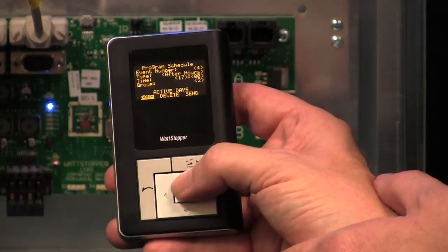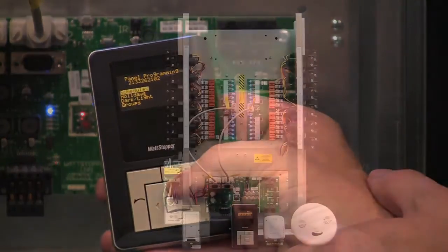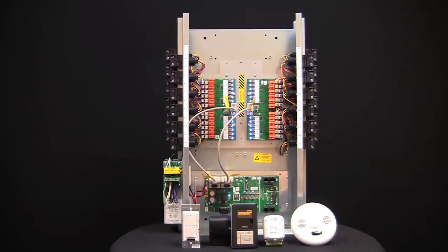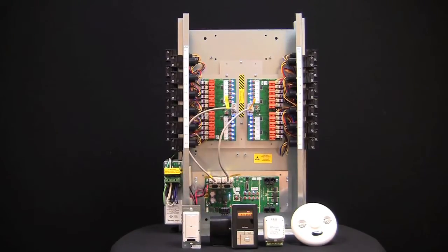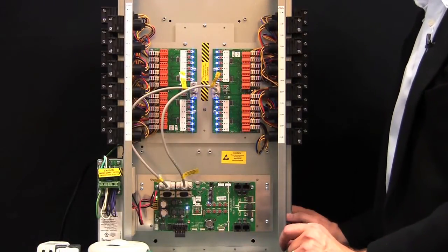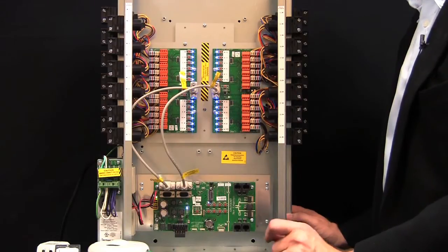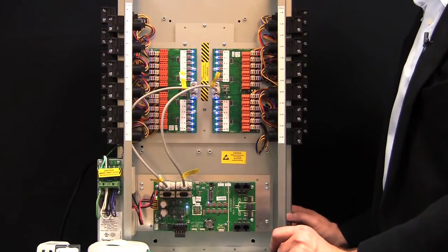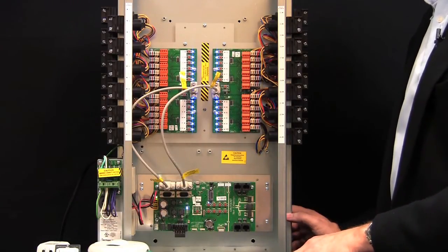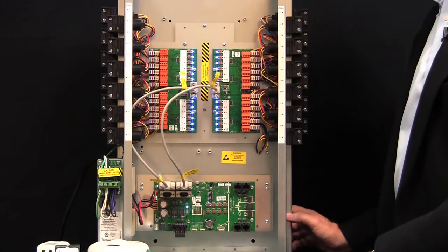We're all done, so I'm going to say done now for these 2 schedules. So what we've done inside this panel is we've used the normal hours and after hours commands to set up a schedule for group number 2. The settings for the group actually will dictate what happens when the loads go to normal hours and when the loads go to after hours. So to review, we've now got 2 different groups that are set up. Group number 1 is following a simple on and off schedule. Group number 2 is actually using the more advanced normal hours and after hours, where we can describe what the parameters are for each part of the day and use that to schedule.